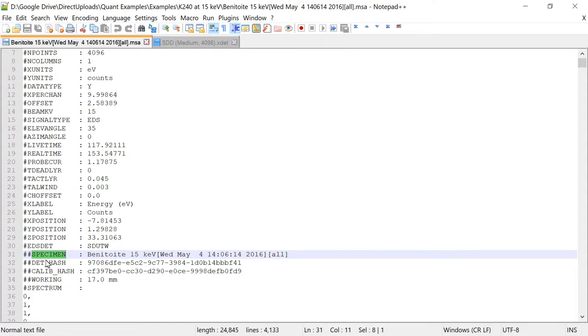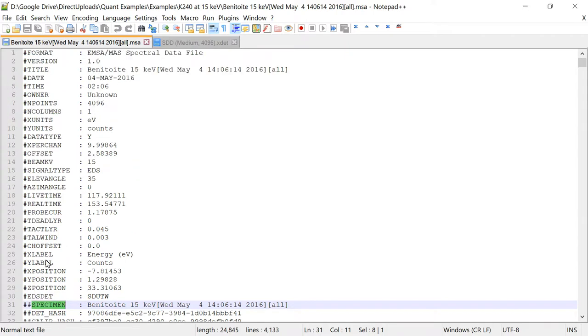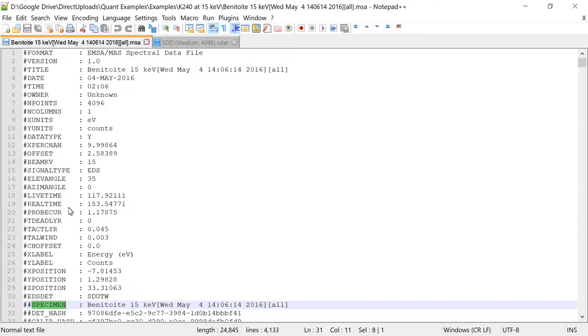You can actually include other pieces of information. DTSA2 defines some special tags that are identified by these double hashes. This is part of the standard that you can add special custom items using the double hashes. Some of the additional information you can add into the spectrum are things like the composition of the material from which the spectrum was collected. In the ideal world, all the necessary data would be in the file and all that data would be correct. What we're going to do is show you how, if some of this information is missing, that you can add it into the file using the DTSA2 software. You really never need to edit one of these files directly.